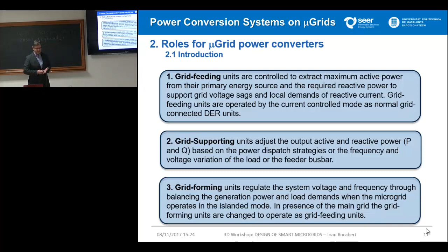I'm going to go into more detail on that. The grid feeding ones are those that, as I explained, are based on constant power injection, or maximum power point tracking, okay, and give the converter a reference current as a function of P and Q. And this P and Q reference is given by an MPPT algorithm or by the secondary control. Okay? And this is one of the main roles of the converters that are actually connected to the grid.